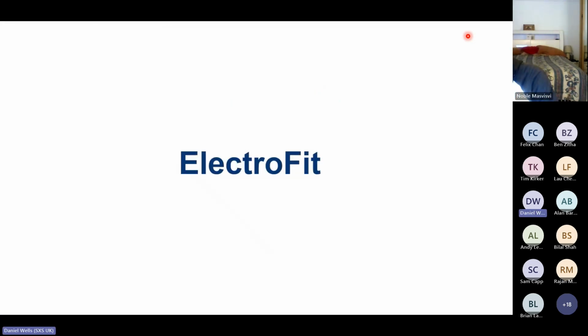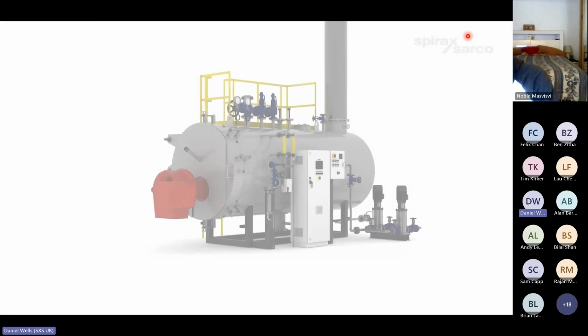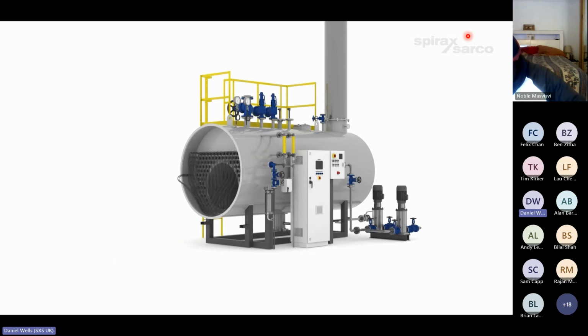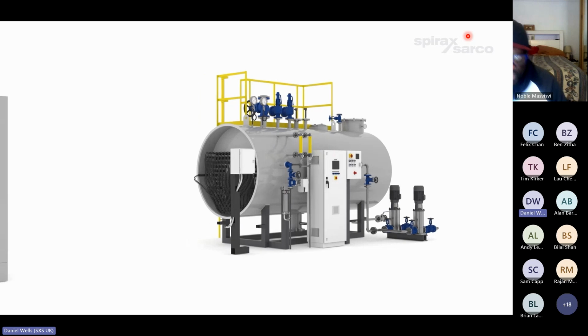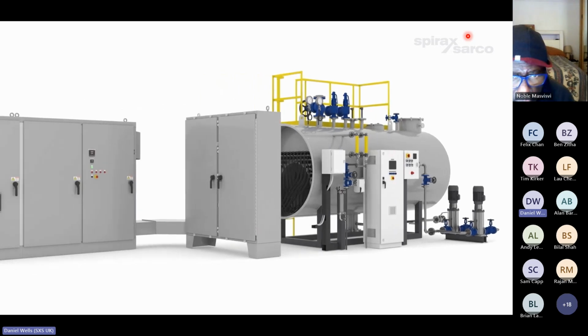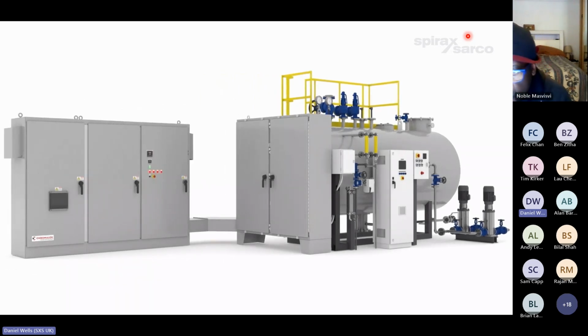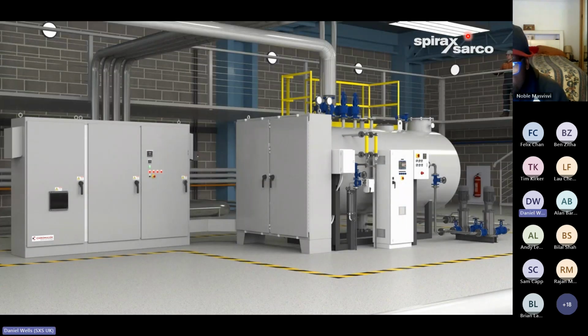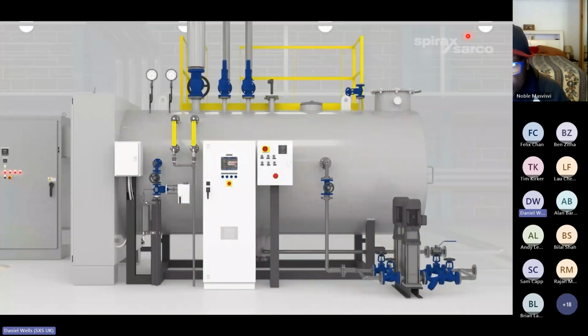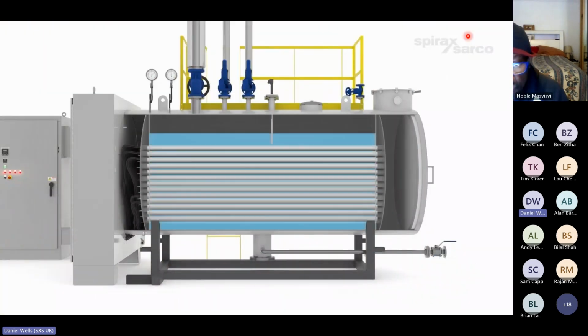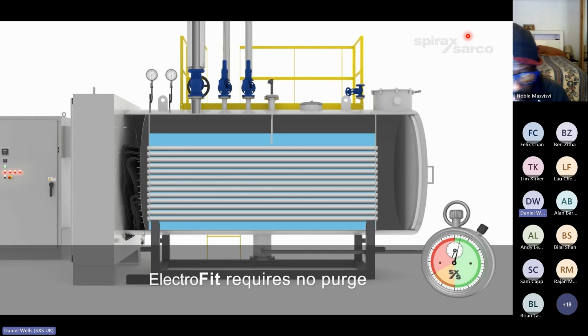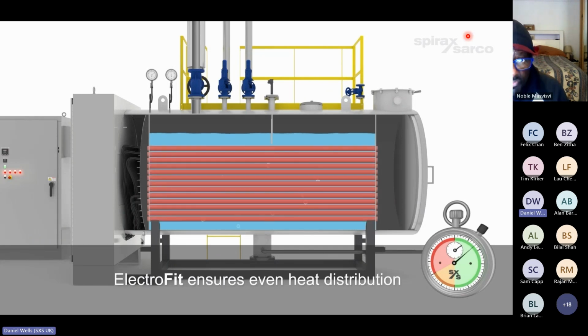So a little animation for you here, just to demonstrate that concept. We take the front door off the boiler. We get rid of the natural gas burner. We don't need it. We replace the natural gas burner with a control panel. We cap off the flue. So we're bringing electricity onto the control panel. It can be high voltage. It can be medium voltage electricity. It really depends upon the client's preference and the nature of the electrical infrastructure locally.